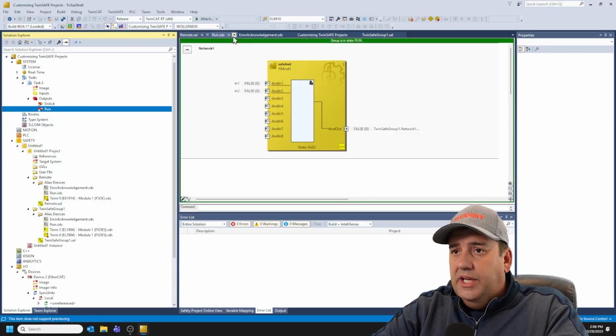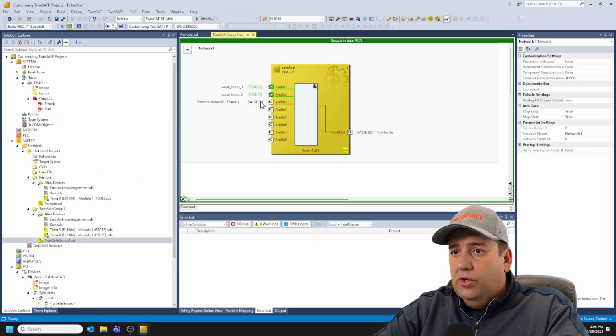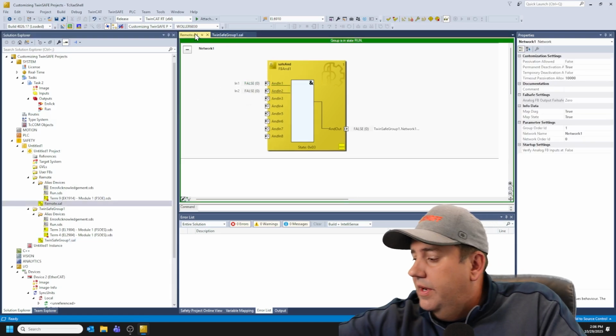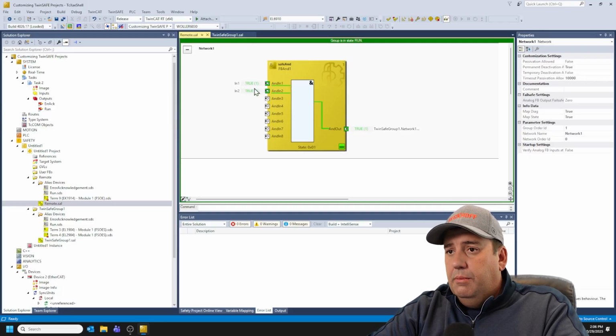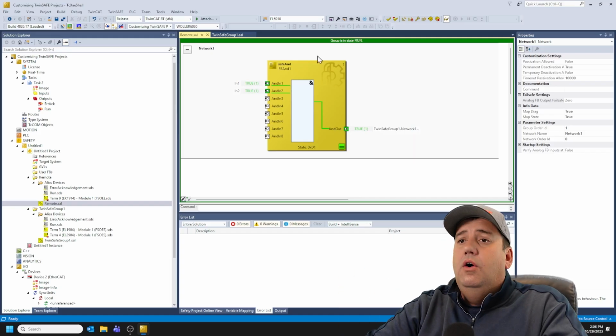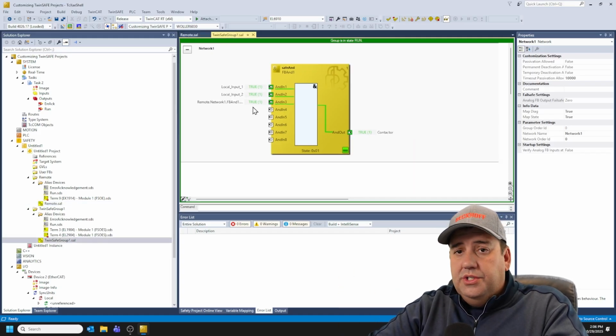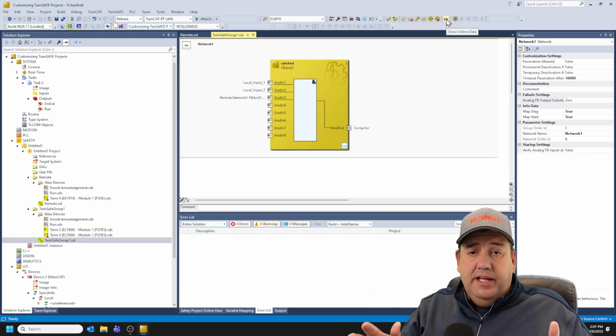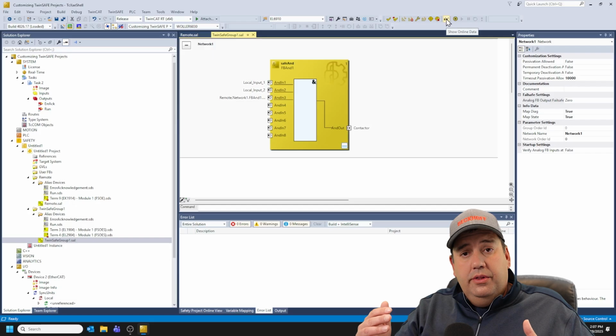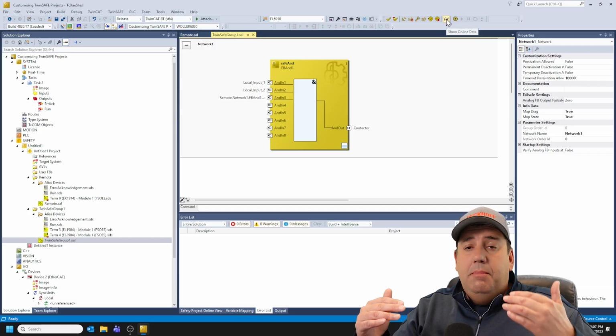So our remote SAL is in run, and our local SAL is in run. Now, if I bring those true, we can see the two coming in through the AND block, and then our virtual line over to the other group, we see it as true. Now, the only customization setting that can be changed while the groups are in run is passivation.